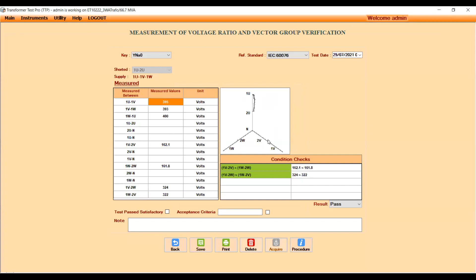Okay. You can see the key that gets generated automatically. There are two vector groups in this particular job, so you can see them, how they are. You can see the reference standard, the test type, and most of the ratio meters these days come with automatic detection of the vector group, and then it comes automatically. Otherwise, you'll be required to measure.